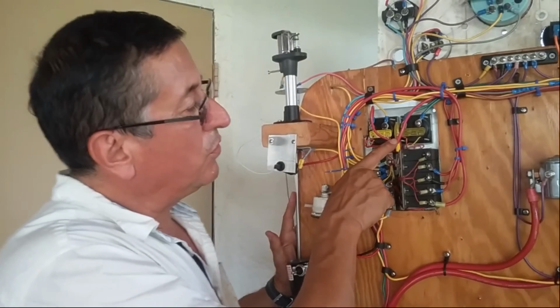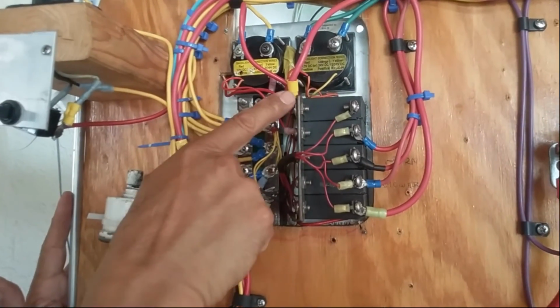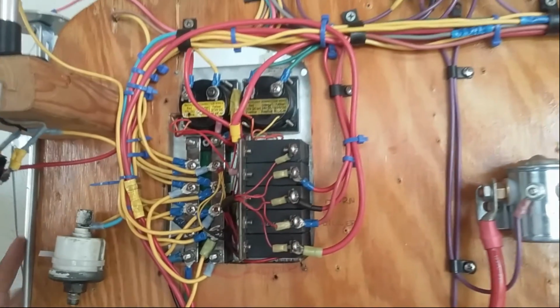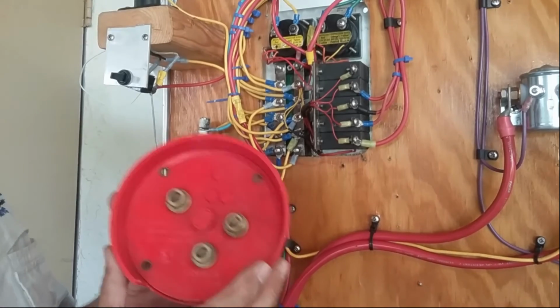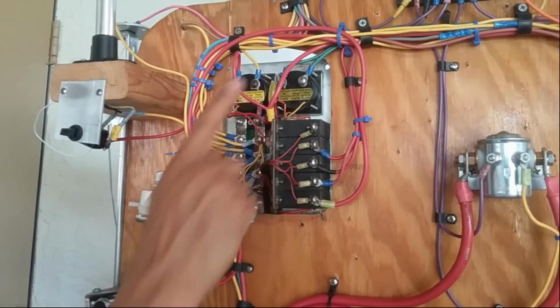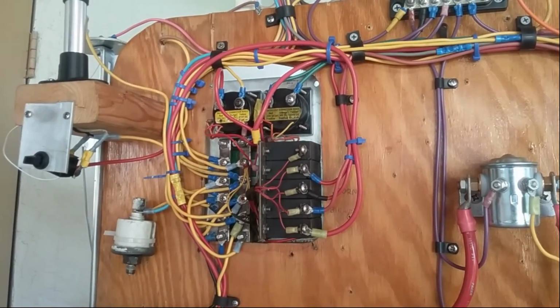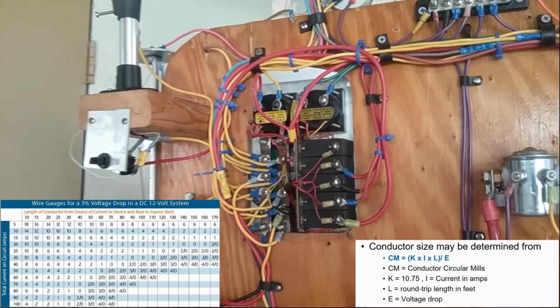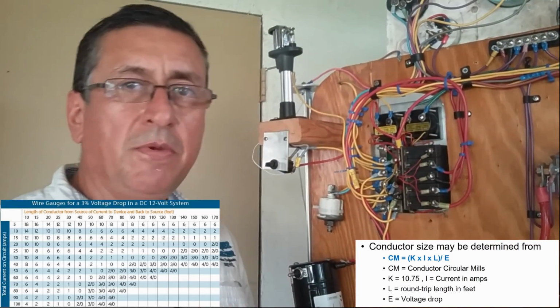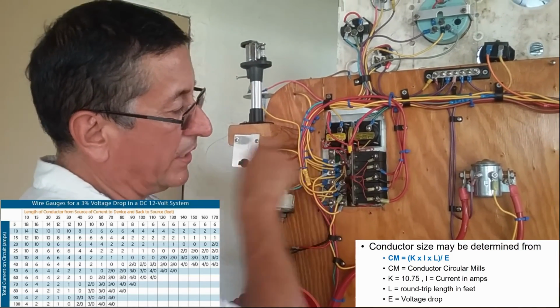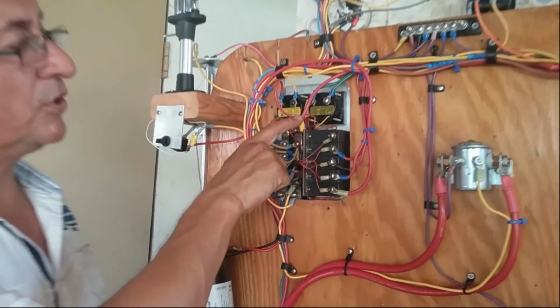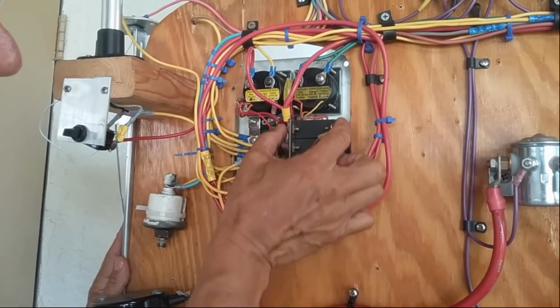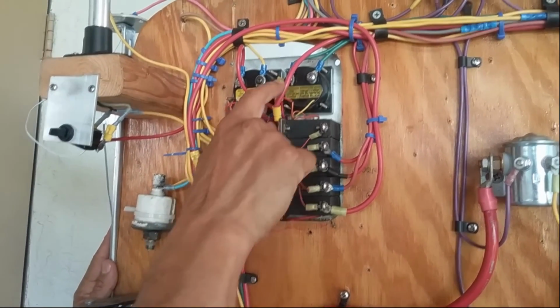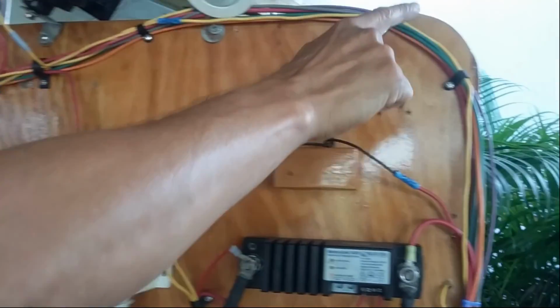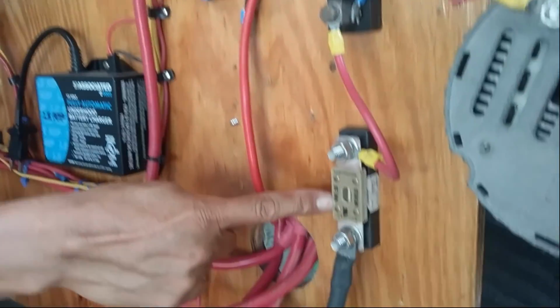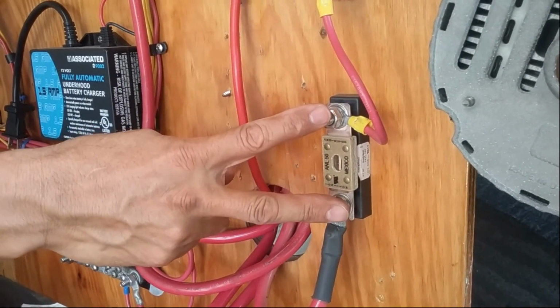Okay, we are going to follow the feeder cable, the cable with the power coming in. That cable is coming, like I explained, from the common of the battery switch selector. The gauge of this wire is calculated according to the capacity of those breakers, using the formula that you have on the screen right now, or the tables in the ABYC study guide. All right, this cable is protected with a fuse. According to the capacity in amps, this cable is protected with a fuse. And this is the fuse used to protect the panel.